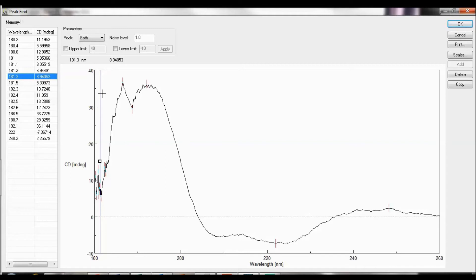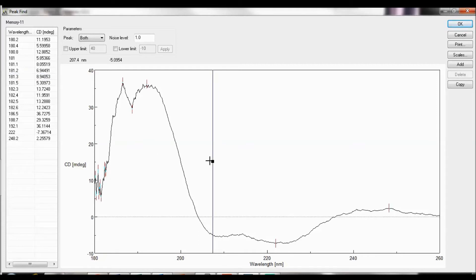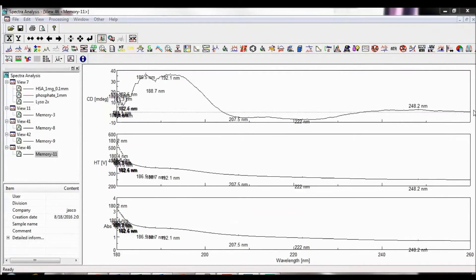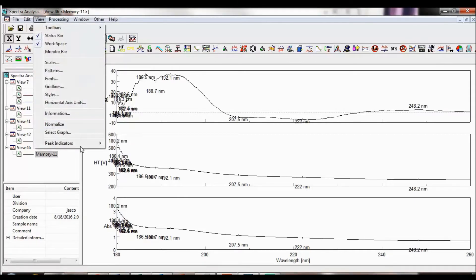You can also select a peak to add by either selecting the wavelength with the cursor, or moving boxes in the spectrum with the tweezer icon. Then select the Add button on the right-hand side of the screen. Peaks can be deleted by selecting the peak and then clicking Delete. The peak table results can also be copied to the clipboard. Click OK to accept the peak find results and create a new memory. The new memory may or may not include peak indicators depending on what was specified earlier. To add or edit the peak indicators, either select the peak indicators icon in the View Command toolbar or go to View, Peak Indicators.